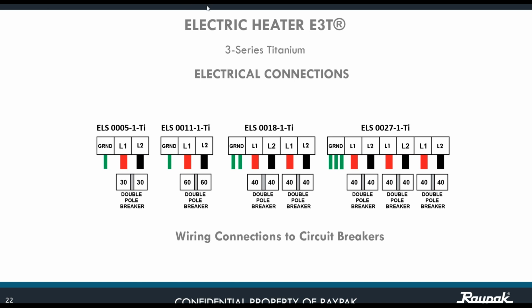If you can see here, for the 5.5 kilowatts, you have ground, L1, L2, going connected to a double pole breaker. For the 11, you have L1, L2, a double pole breaker of 60, and you have ground. For the 18 kilowatts, now you have two L1s and two L2s, all of them connected to their respective double pole breaker. You have two 240s, well, it's a double one, and two grounds. So that's the reason why I was referring to it as a wire set.